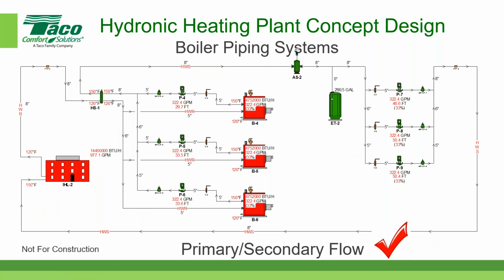How do you determine what delta T to use on a system? Great question. Oh, that's a great question. That also requires some first cost, operating cost analysis, because most heating systems in the past were designed around a 20-degree delta T, which meant that in most cases, the hot water went out to the terminal devices at 180 degrees, which was a pretty common number, and it came back at 160 for a 20-degree delta T. And that meant that the selection for the terminal devices was dependent on a 20-degree delta T with an entering water temperature of 180 degrees. So their capacity for selection purposes was based on those parameters.